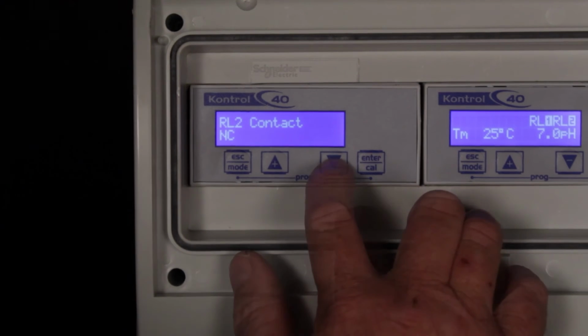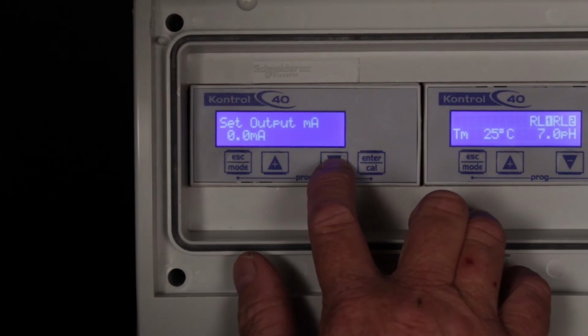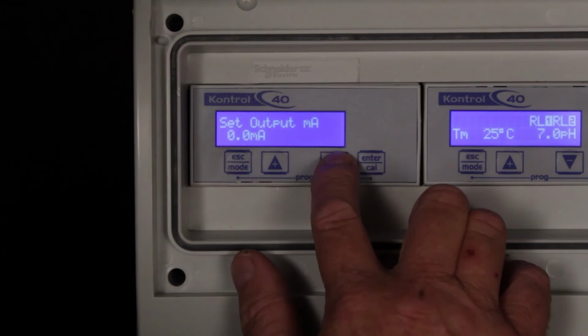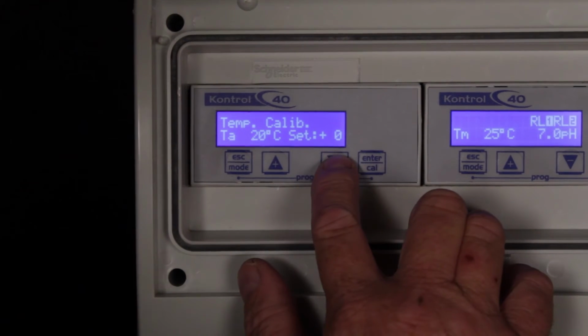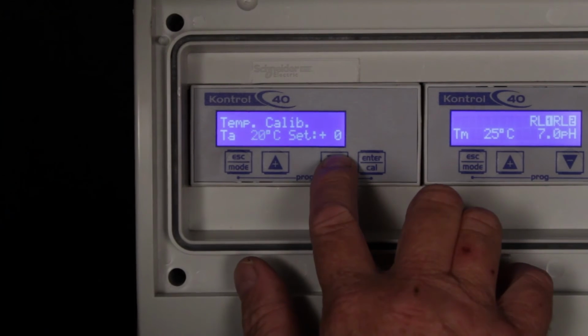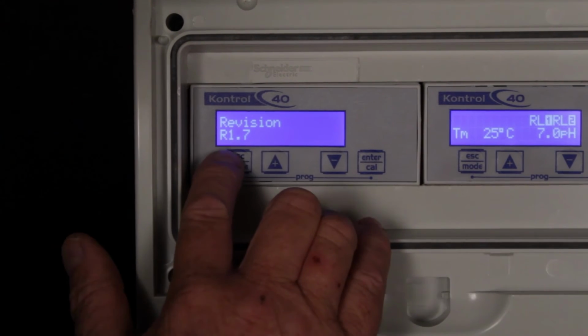dosing to lock out our pH controller during EC dosing. Press the minus button so you can get to temperature calibrate. Here you can calibrate your temperature probe in the EC probe. Now exit and always save changed values.